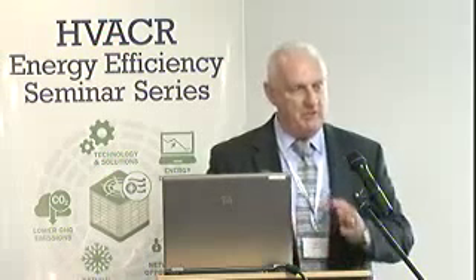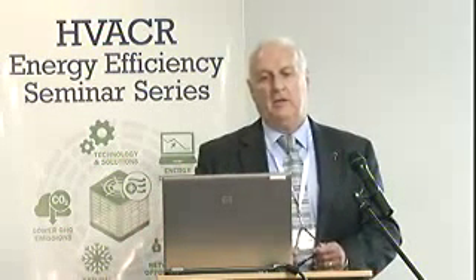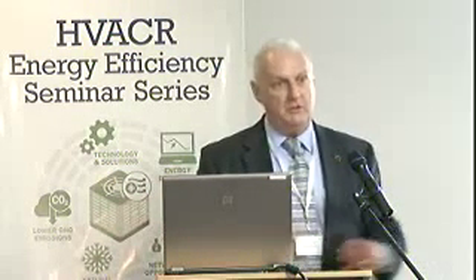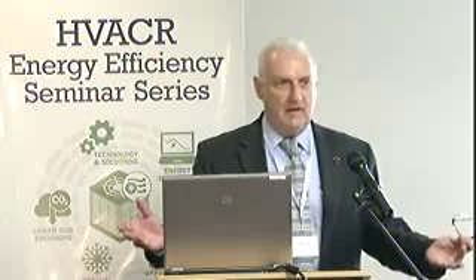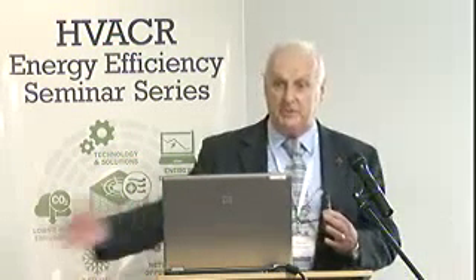So that means in the range of 254 volts when we're measuring line to neutral to 216 volts, the Ausgrids, Energex, Essential Energies are all quite legitimately supply you at whatever voltage in that range they like at the metering point, at your main switchboard. And then AS3000 comes in and there's another potential 5% voltage drop within your facilities.